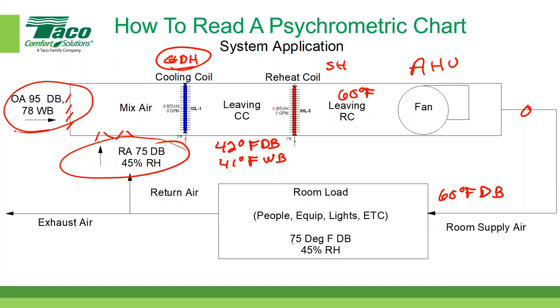And the room is set at 75 degrees dry bulb, 45% relative humidity. That is actually going to be the set point. So whatever my temperature and humidity set point is over here, that's going to be the same conditions as the return air. Some of that air will be exhausted, and then some of it will be returned. So there's the whole cycle in terms of a basic system application.